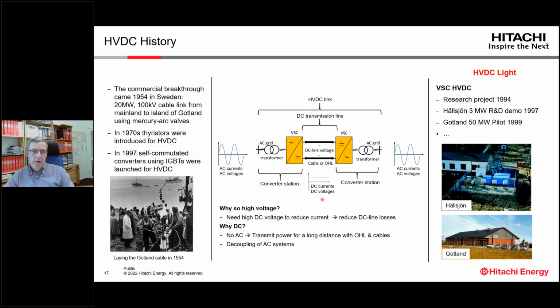So why use high voltage DC? Here you could see a scheme how it works. We connect 2 different AC grids, and we want to use the high voltage DC to reduce the current. When we reduce the current, we also reduce the losses in the DC line. And DC then of course have no AC. By that we can transmit power for a long distance with overhead lines and with cables. And we also decouple AC systems where we don't have the same frequency or they are not synchronized.